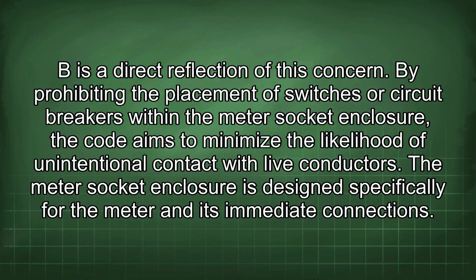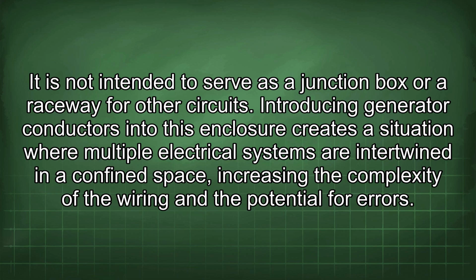The meter socket enclosure is designed specifically for the meter and its immediate connections. It is not intended to serve as a junction box or a raceway for other circuits. Introducing generator conductors into this enclosure creates a situation where multiple electrical systems are intertwined in a confined space, increasing the complexity of the wiring and the potential for errors.